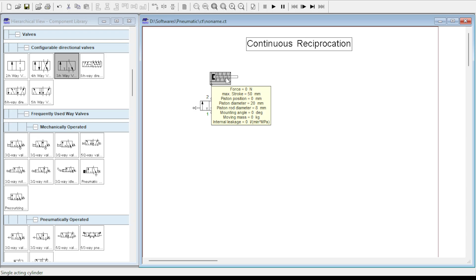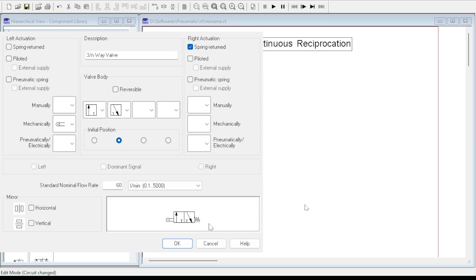So again, I'll take a 3x2 DCV and I can configure this 3x2 DCV in order to make it a roller actuated spring return DCV. The left hand side actuation, I'll choose to be roller actuated under mechanical section, and the right side actuation or the return mechanism will be spring. So the DCV that is used for sensing the extended limits of the cylinder's actuation will be a roller actuated 3x2 spring return DCV.